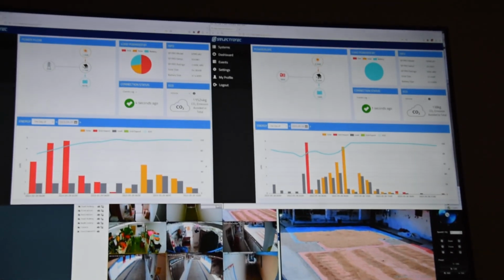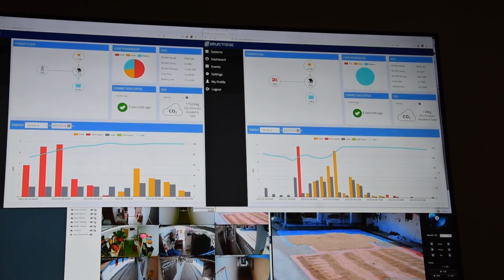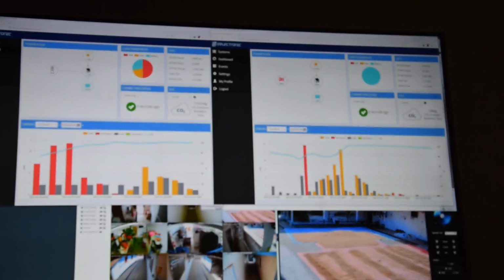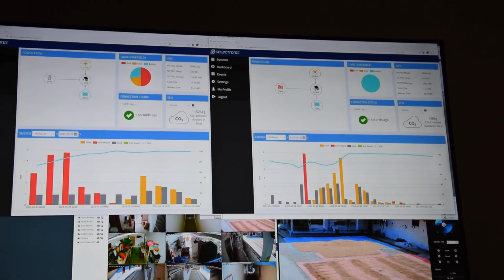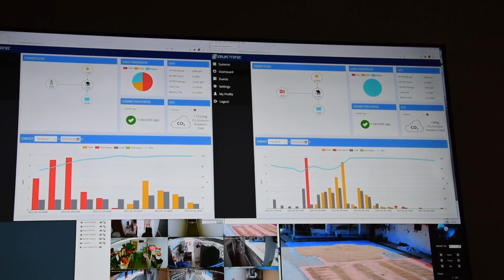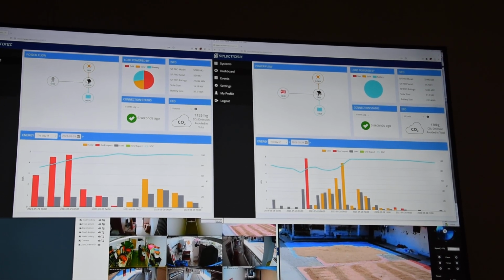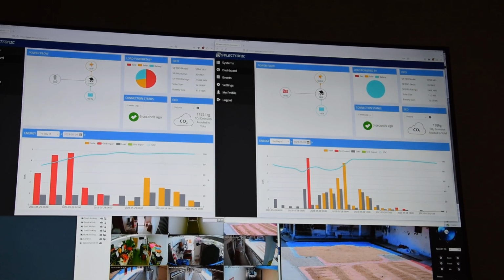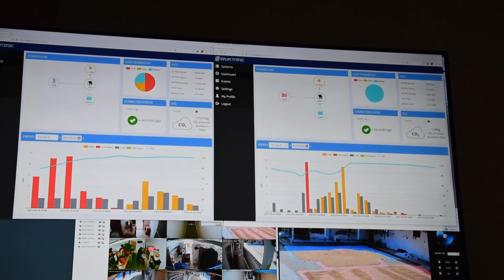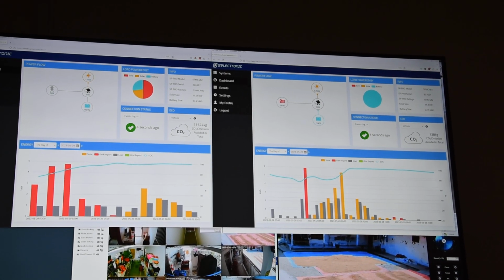So there's either a configuration problem or a firmware problem, and Asep thinks it's a firmware issue, and he's logged a call with Selectronic over it. But the generator was running at 2 o'clock this morning, and then it was running again at 3 and ran for about 50 minutes. And so I don't know whether that fuel tank's empty or not. It could well be, which may make for trouble starting the engine next time after we've filled it with diesel. So yeah, not ideal, but teething troubles. Complex systems have complex problems.